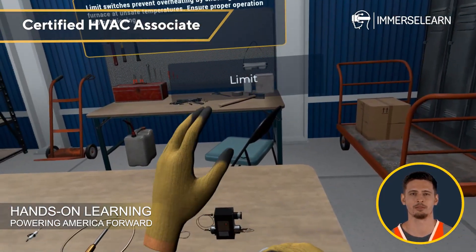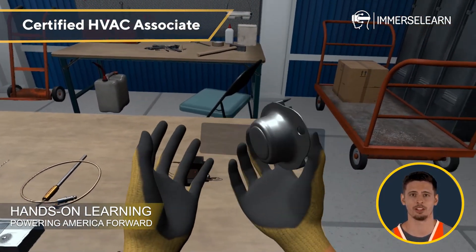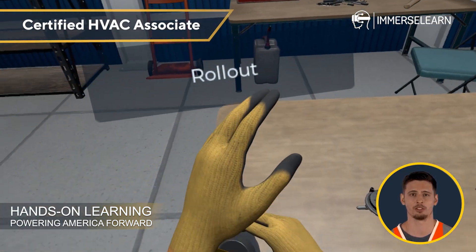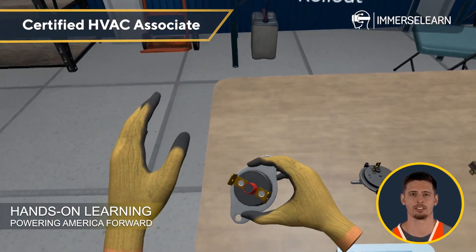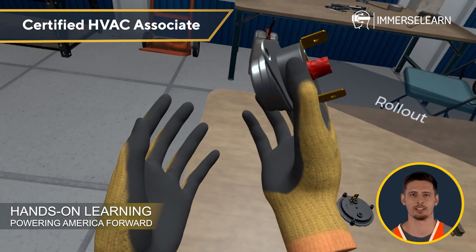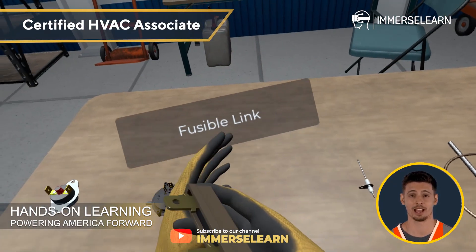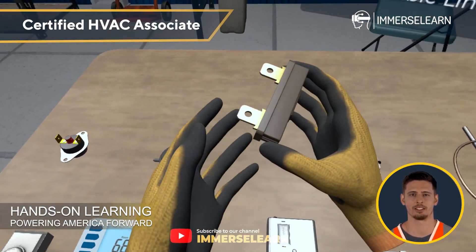The limit switch plays a vital role in preventing overheating by shutting off the furnace at unsafe temperatures. The rollout switch ensures flames stay contained, so checking for damage or dirt buildup is essential. Pressure switches monitor air flow and system pressure, ensuring safe operation, while fusible links act as safety breakers, cutting off power in case of excessive heat.